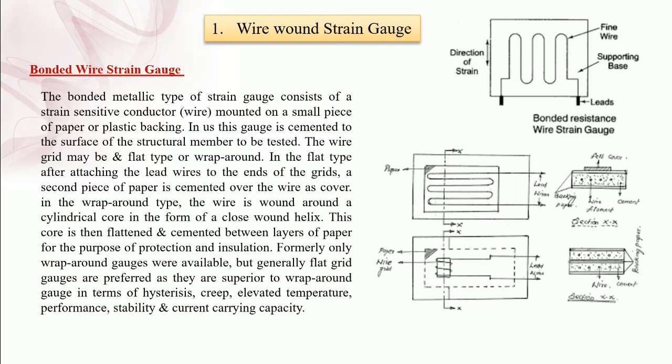Such a unit may be mounted upon or incorporated in mechanical elements or structures whose deformation under stress is to be determined. While there are no limits on the basic value which may be selected for this strain gauge resistance, a typical example you can take is of the order of 100 to 500 ohm.